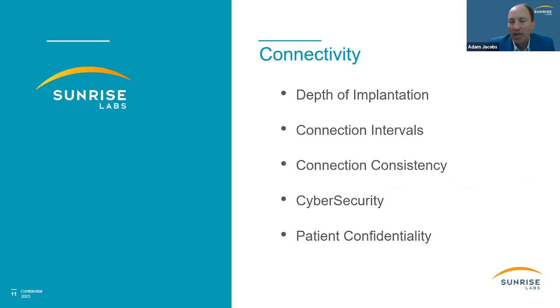A couple more comments about connectivity. The depth of implantation does matter. Basically, the deeper you go, the more attenuation you have. People are bags of salt water, and it attenuates the RF. However, if you're subcutaneous, which is most implanted medical devices, say a pacemaker, which is not that deep, then the regular Bluetooth Low Energy 2.4 gigahertz frequencies work just fine. If you want to go much deeper, there are 400 and 900 megahertz bands that have greater penetration, but they have lower data rates. So the depth of implantation does matter.